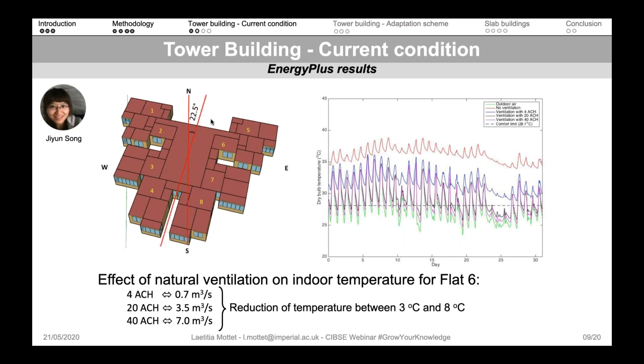So we wondered, why don't people just open their windows to reduce the indoor temperature? What's the problem with this building? We ran some CFD simulations and got access to the pressure field along the facades of the building. Based on that, we could compute the maximum ventilation rate achievable in a specific flat from the pressure field along the facade. We found that the maximum flow rate achievable just by opening windows is so low that we'd never bring enough fresh outdoor air indoors to reduce the indoor temperature. So that's just a fact: if they open their windows, they won't achieve thermal comfort at all.